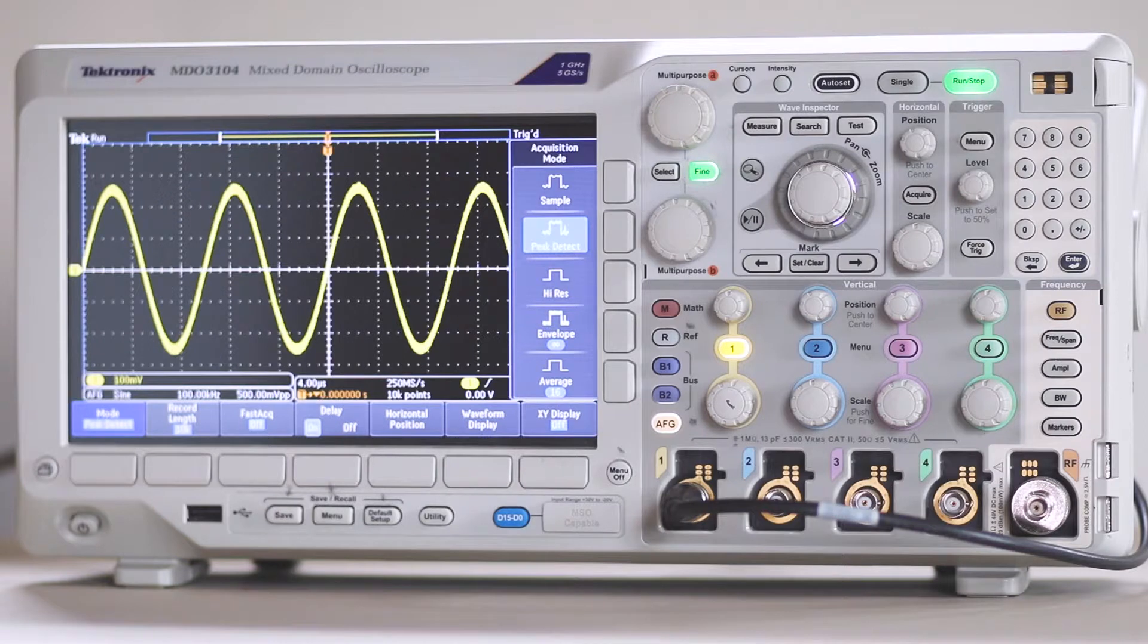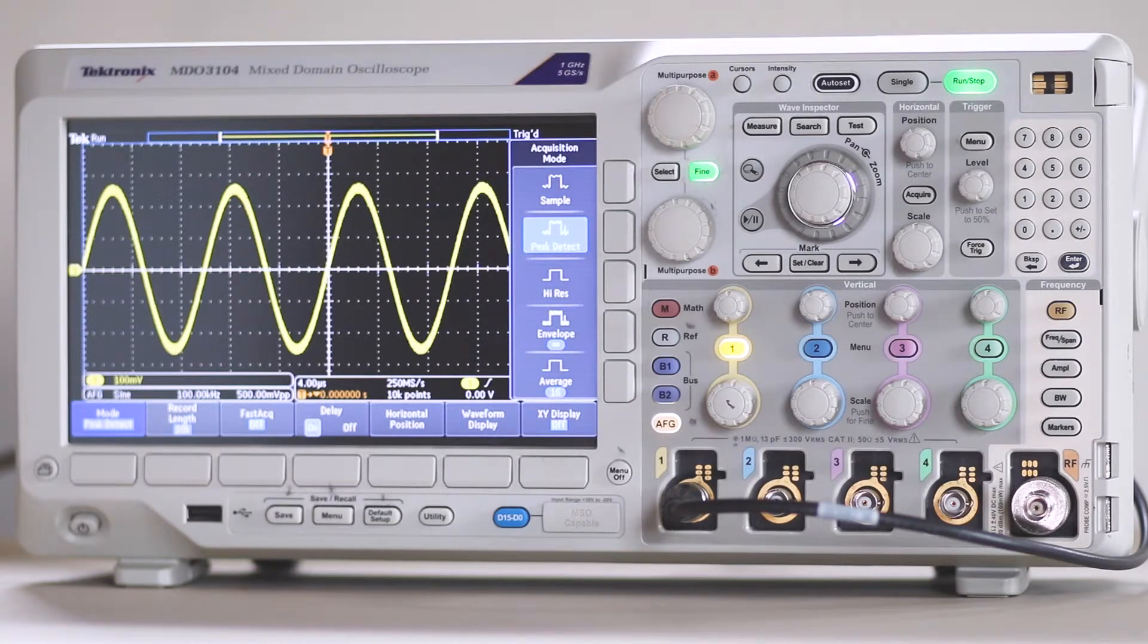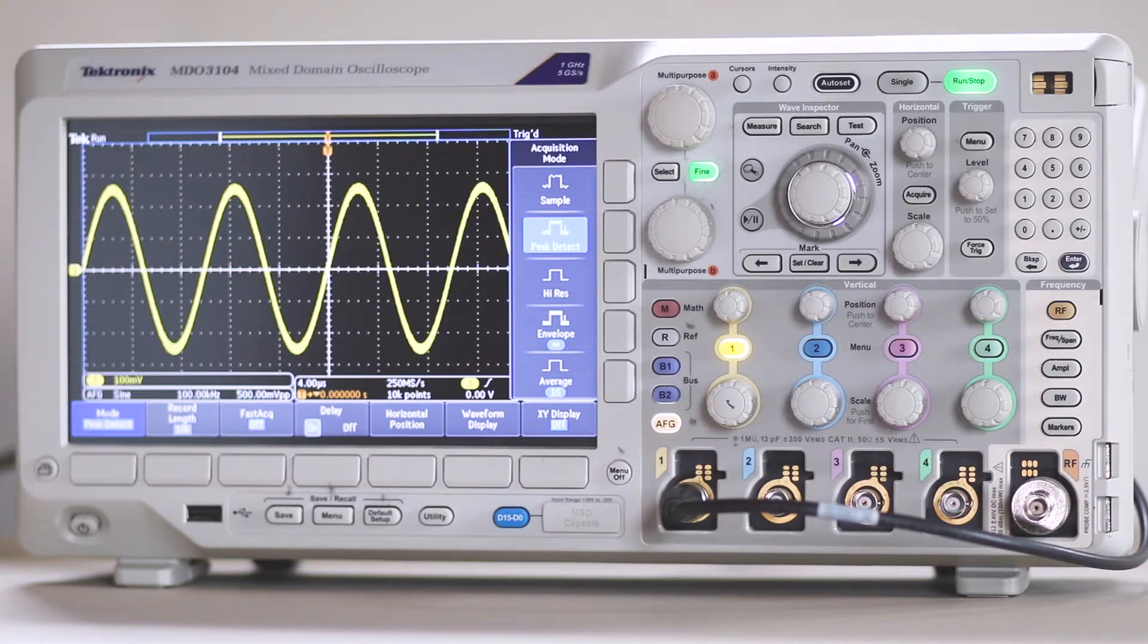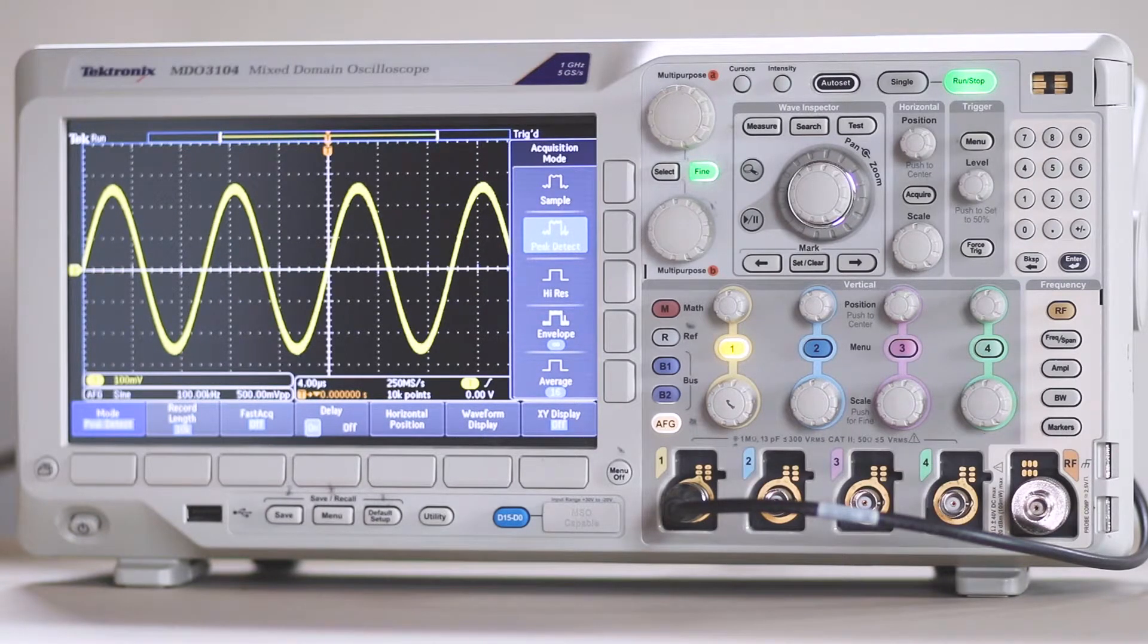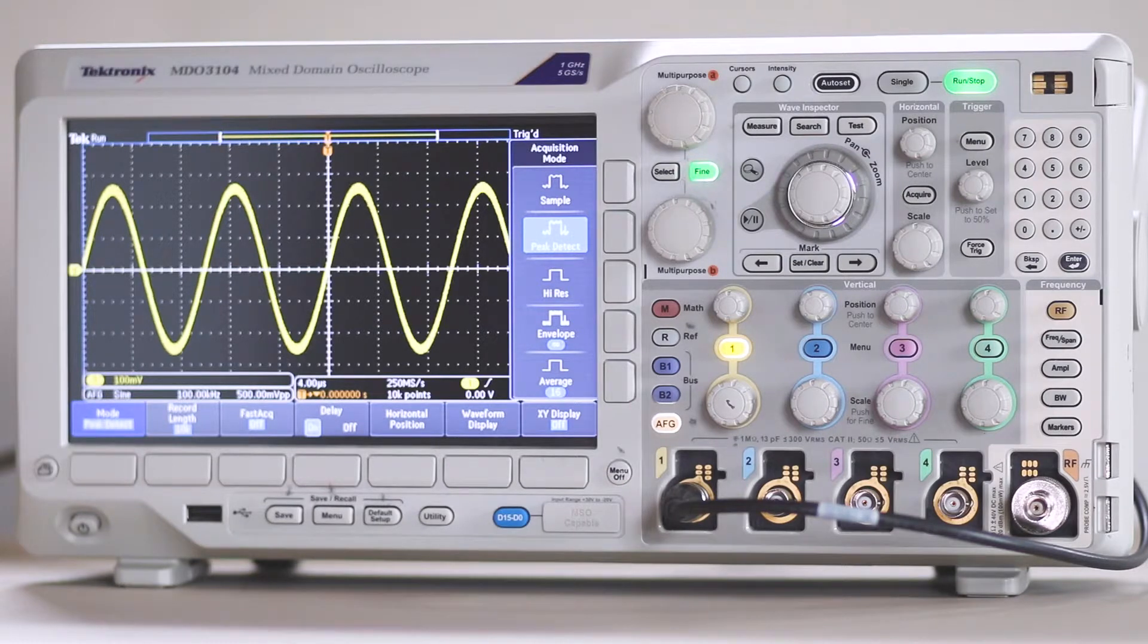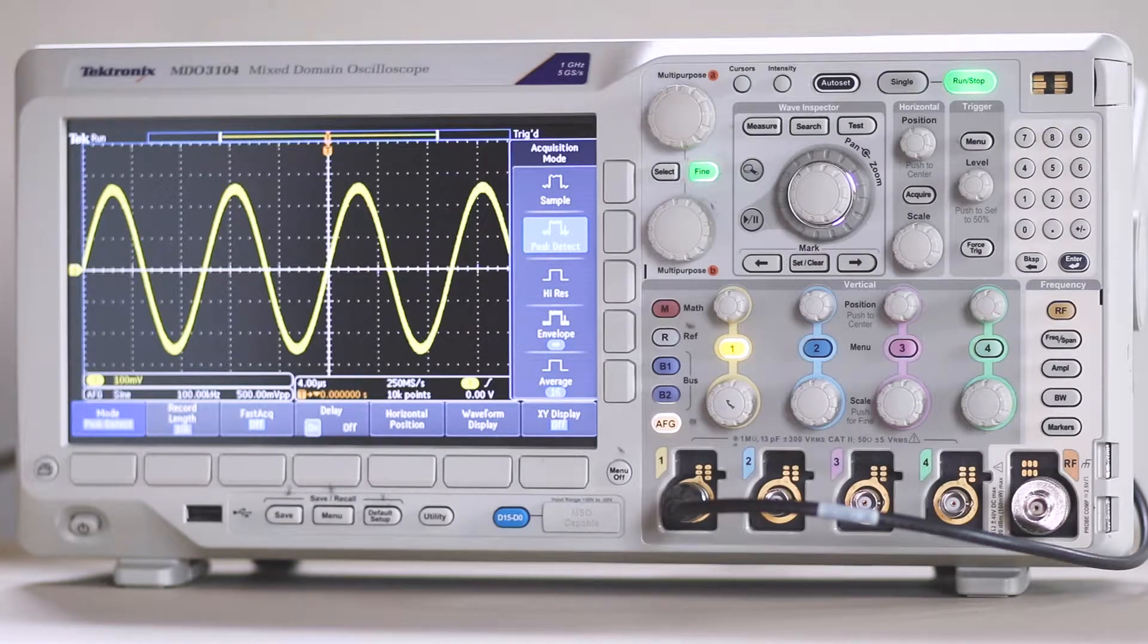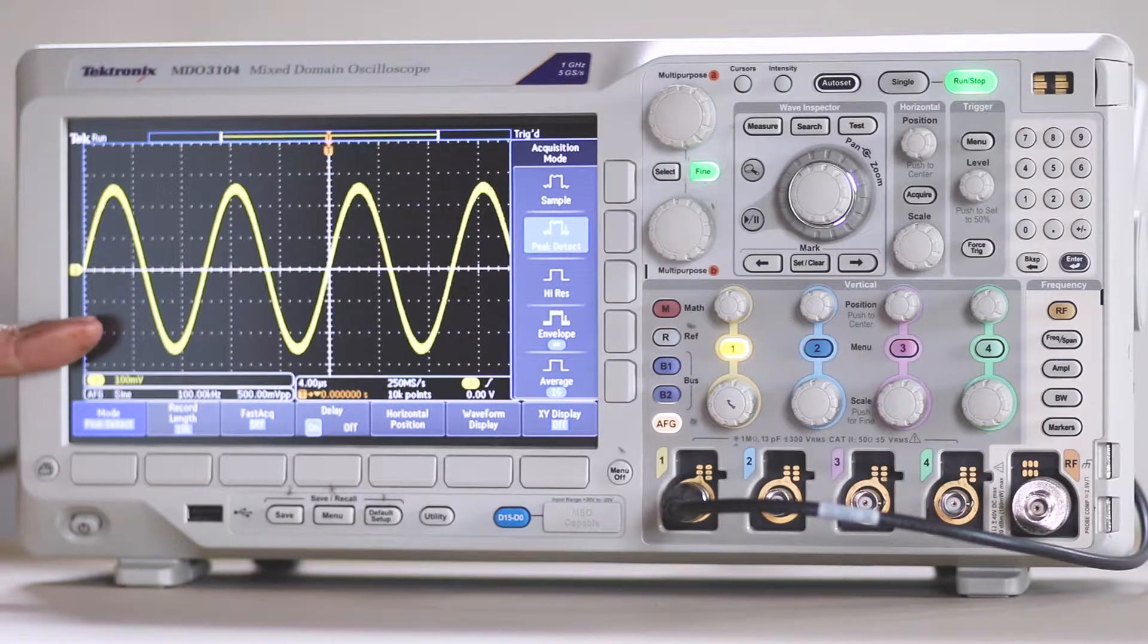which would otherwise be very difficult for the oscilloscope to see. High-res mode is a technique for eliminating noise that may contaminate a signal. Like Peak Detect, this method functions in real-time, non-interpolated sampling. By temporarily limiting the bandwidth, broad-spectrum noise is reduced, allowing the genuine signal to be seen.